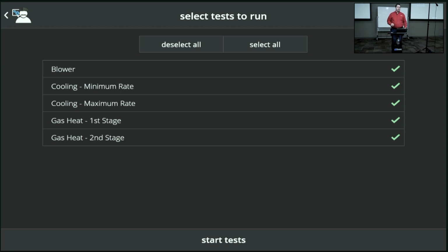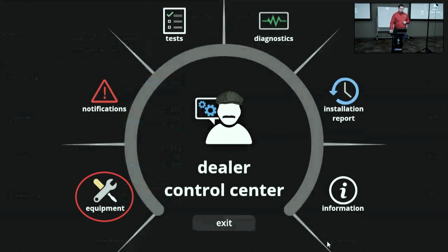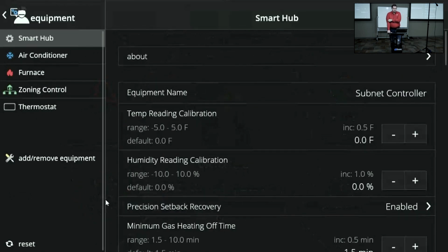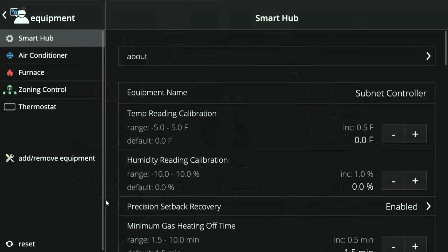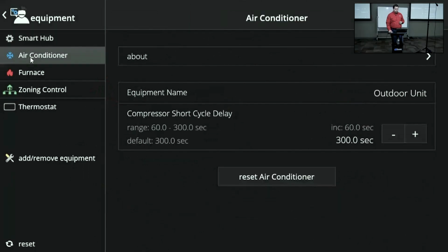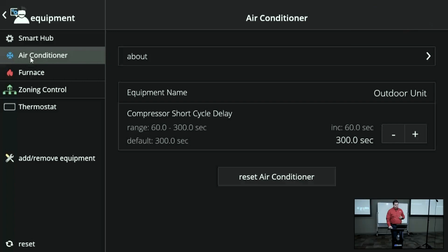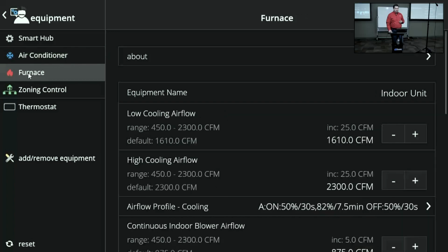So you can test each one of these functions. Again, you can go back into the install setup here and test any of these functions. If you want to test the blower on its own, cooling at minimum or maximum rate on a variable system, or stage 1 or stage 2 in the multi-stage system. Same thing with your gas heat. You can uncheck those and select them individually if you wanted to do that. In the equipment tab, it's going to give us our different menus to make adjustments in the system. Most of what you're going to need to change there is in the Smart Hub, air conditioner, and furnace tab. And again, there's a lot that you can change, not a lot that you have to change.